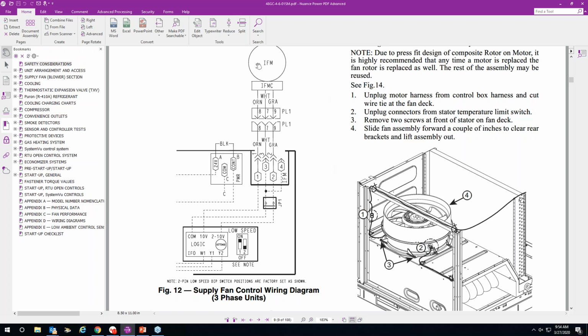Now, if I check my orange wire and I'm not getting 10 volts DC out of the motor, I'm going to do the same thing. I'm going to check all these connections here, this Molex plug connection, and if I'm not getting anything out of the fan motor, and I know that I got my line voltage to it, whatever it is, 208, 230, 460, single phase, 3-phase, if I've checked and verified I've got my line power to this thing and it's not generating 10 volts, then my controller, once again, is bad. So it's that easy to troubleshoot. For those of you that do residential heating, this is a lot easier to troubleshoot than an ECM or a variable speed motor on a furnace. So that's all there is to it.